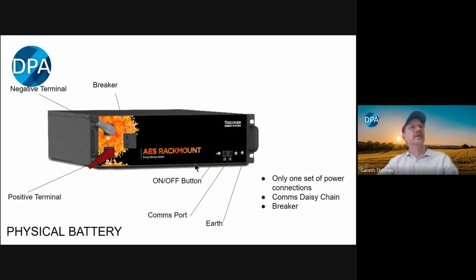The features of the rack mount battery: you've got positive and negative Amphenol connectors on the front, and a 2-pole 100 amp breaker, which meets CC and best practice guide specifications. Most of the time you'll need an additional external breaker because the battery will be inside some sort of cabinet, so it wouldn't be readily accessible. But in some scenarios, if it was readily accessible, it could act as an isolation device because it's 2-pole.